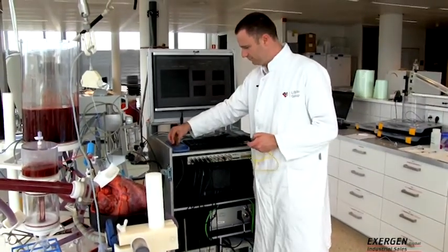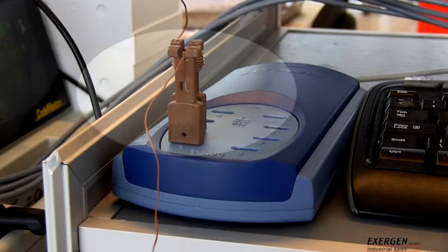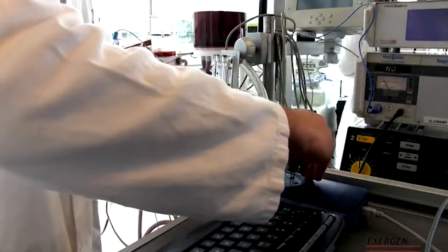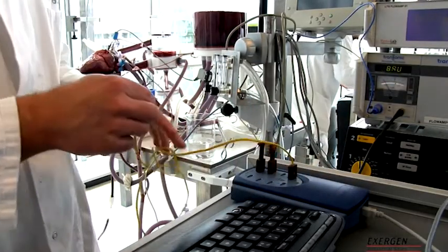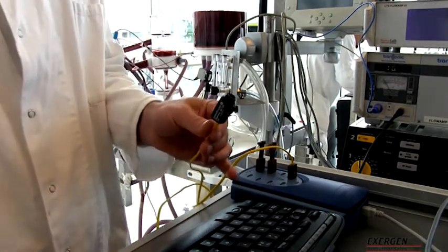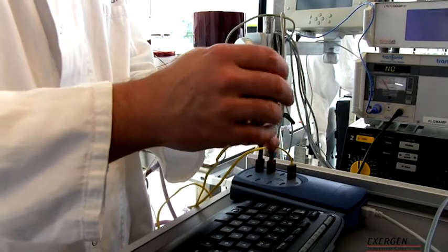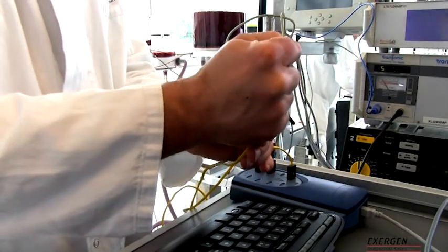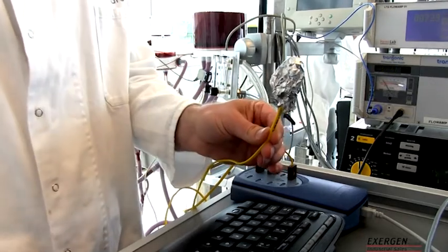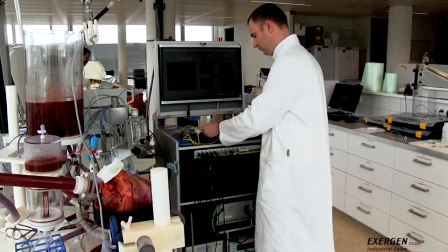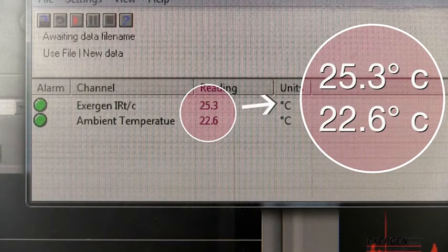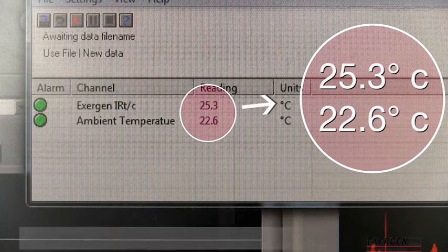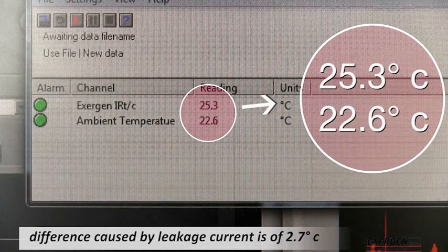You have to take various steps. Measure the ambient temperature with a reference thermometer. Then connect the sensor to the readout device. It is important to wrap the IRTC in aluminum foil to make the sensor blind. It can only see itself, and the temperature that it sees is only the ambient temperature when the sensor is in steady state. The readout device may read a different temperature than the ambient temperature as measured in step 1. This is caused by leakage currents. Adjust the offset in the readout to match the reading as indicated before.